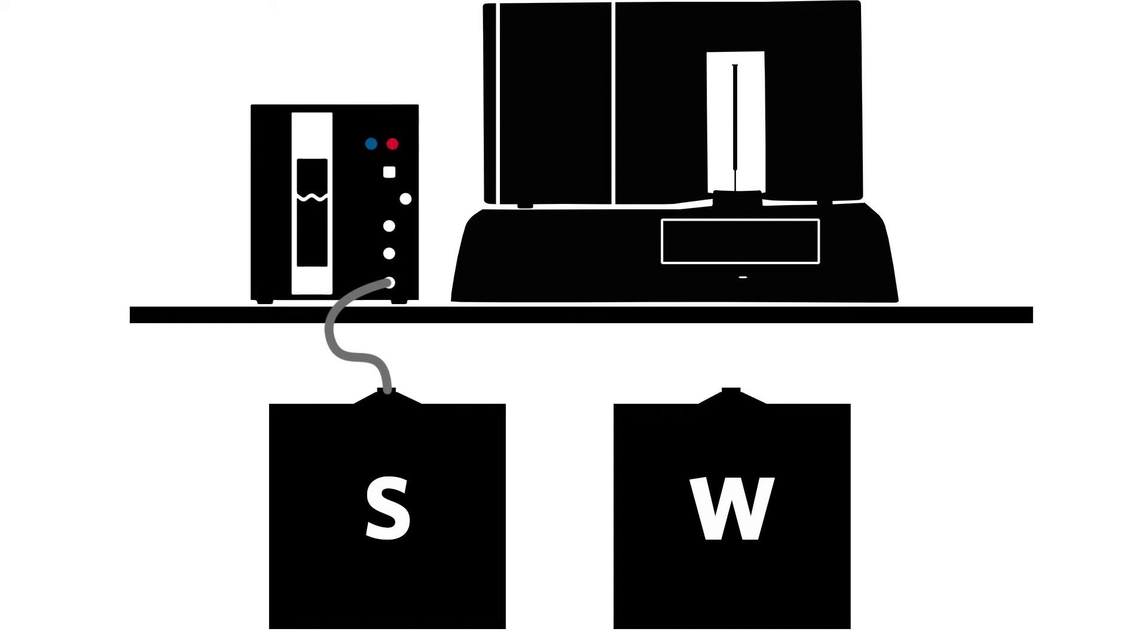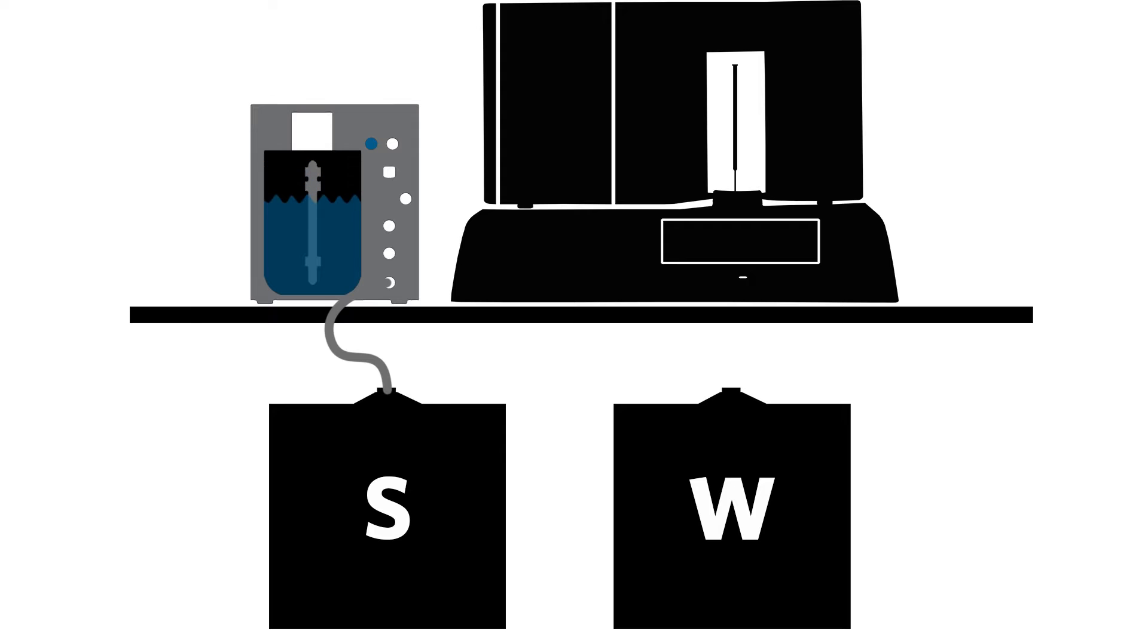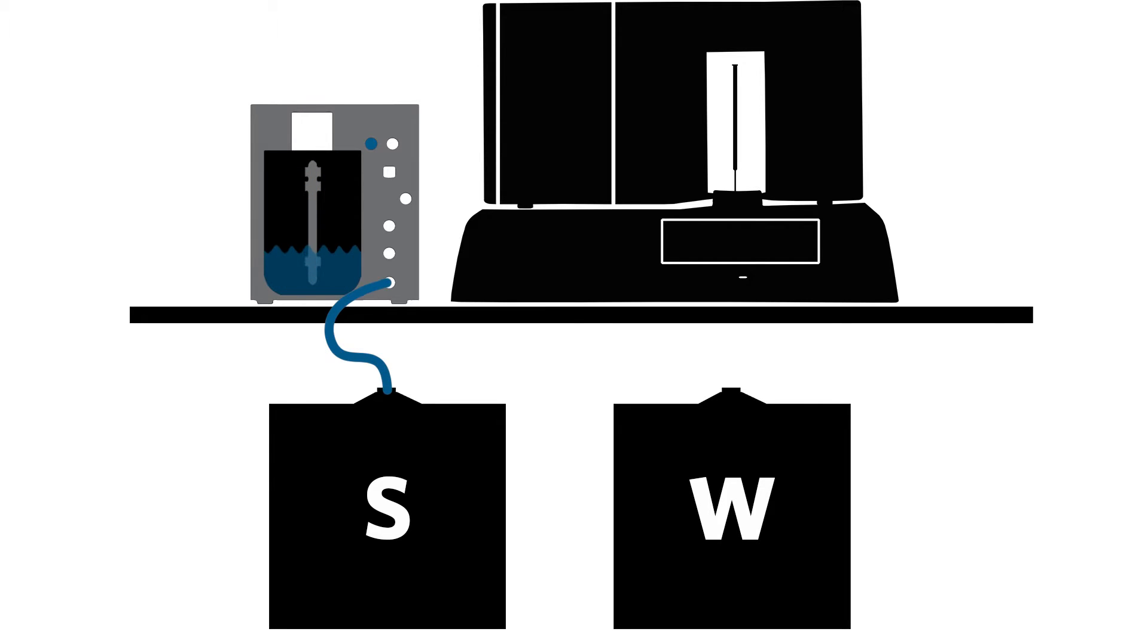If the alarm sounds and beeps quickly, the Sheath Delivery System has overfilled and must be drained completely. Then it needs to refill to its normal level.